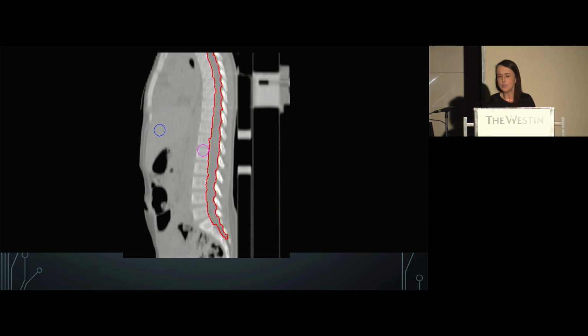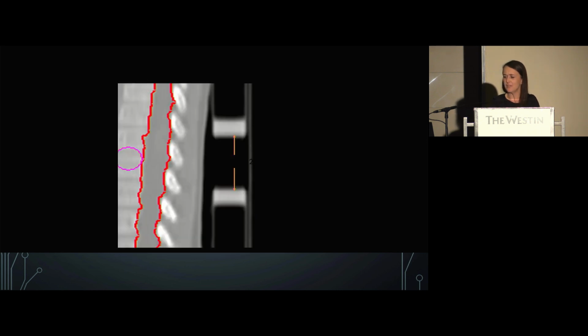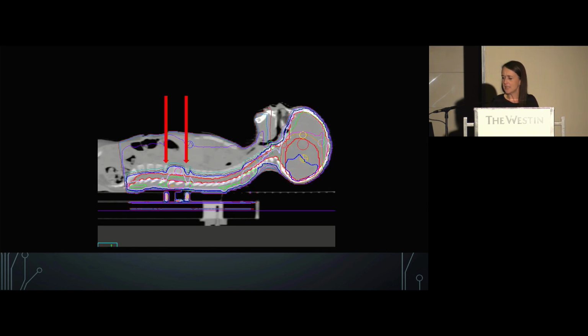So you can see these two white high density inserts in the board. And we started to investigate that. And what you can actually see in the dose distribution is that there was indeed a change in dosimetric effect because of these high density inserts.